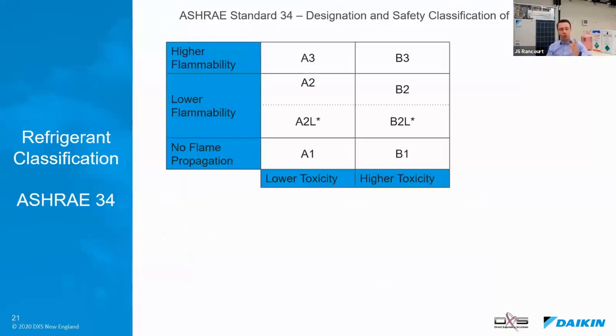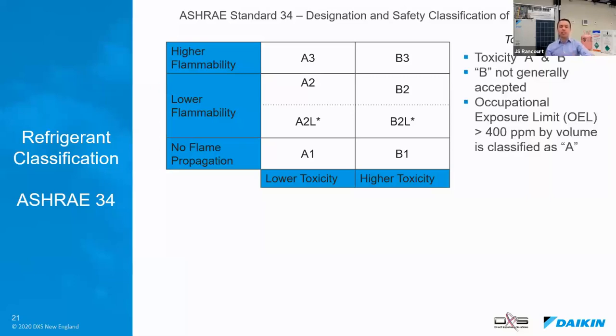They have two different standards. They have ASHRAE 34, which classifies the refrigerants, and it does so in two ways. It classifies it based on toxicity and based on flammability. On toxicity, there's category A and category B, low toxicity, high toxicity. Category B is generally not used. Ammonia is an example of a refrigerant that's a category B toxicity. It's still used in arenas, but there's lots of rules around it.